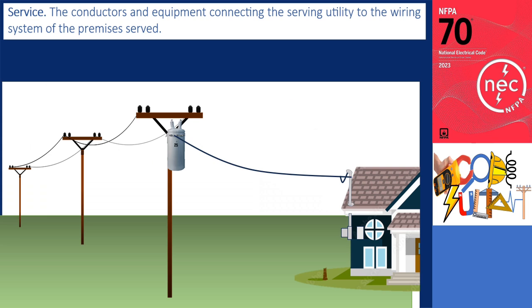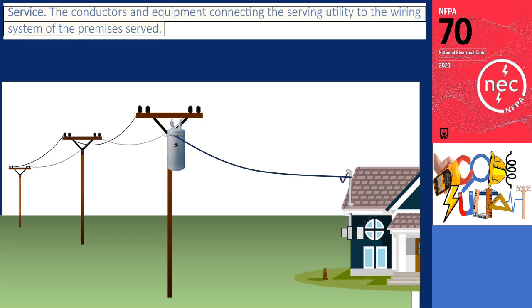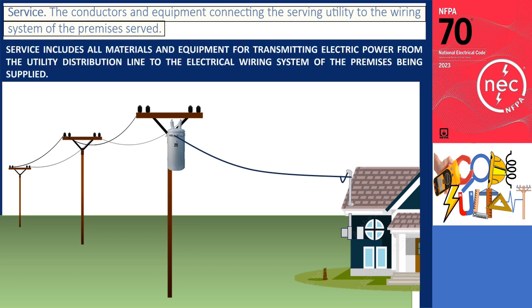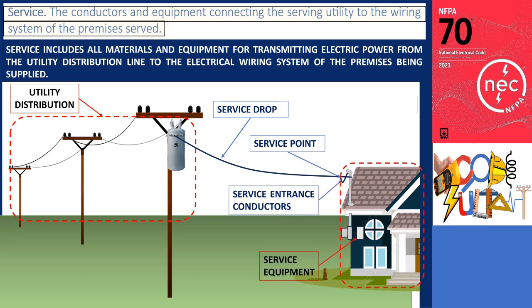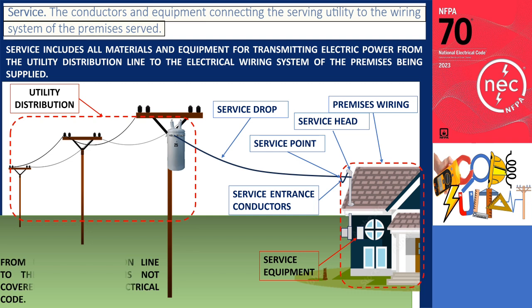Service: the conductors and equipment connecting the serving utility to the wiring system of the premises served. The term 'service' encompasses all the materials and equipment involved in the transmission of electric power from the utility distribution line to the electrical wiring system of the premises being supplied.